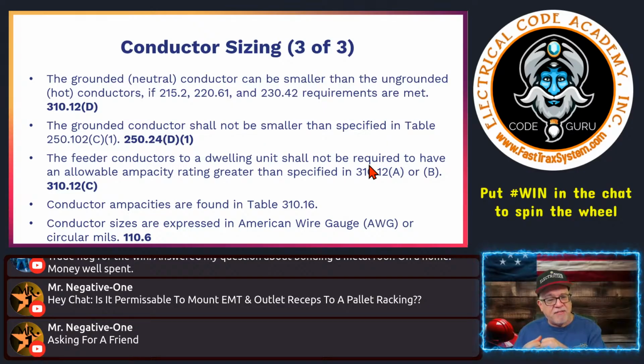You still have the caveat that that panel that's being supplied by that feeder has to handle 100% of that load. So you still have to meet the rules. Okay, so you're running that feeder to that dwelling unit, and all the loads have to be within that dwelling unit. Okay.